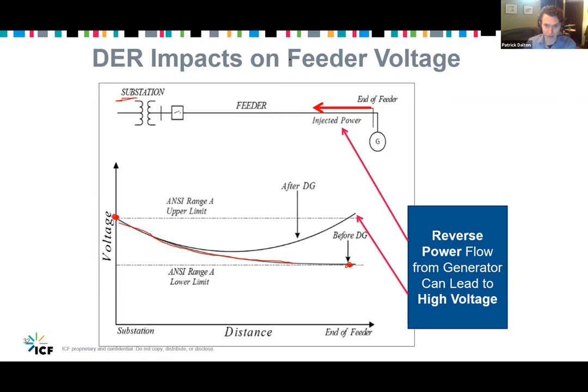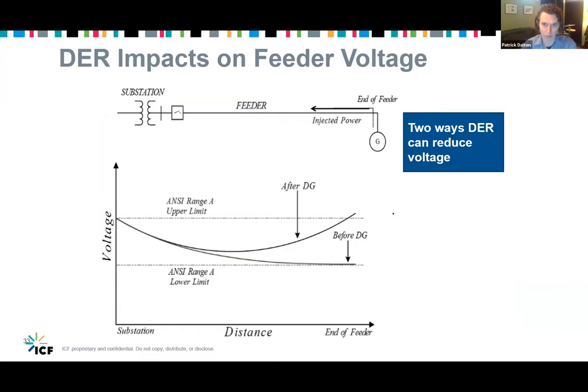If we add a generator at the tail end of the line that injects power in the reverse direction from the normal flow, voltage is raised at the generator location due to that current flowing across an impedance in the other direction. So it's essentially the same physics, but now that we've added a source near the tail end, we can have high voltage.